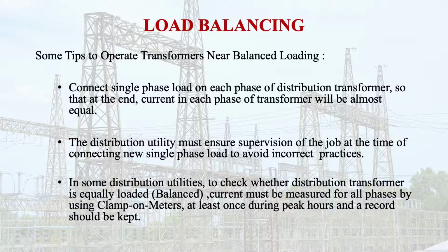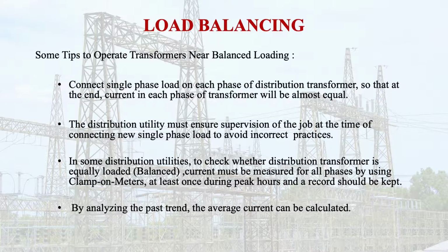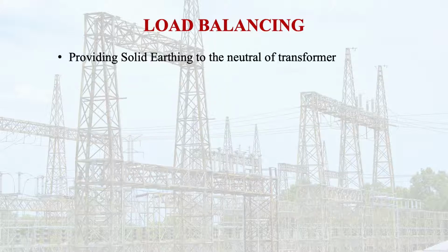In some distribution utilities, transformers do not have current measuring instruments, and hence continuous surveillance cannot be done to check whether the distribution transformer is equally loaded, balanced. In this case, the current must be measured for all the phases using a clamp-on meter at least once during the peak hours, and a record should be kept. By analyzing the past trend, the average current can be calculated.